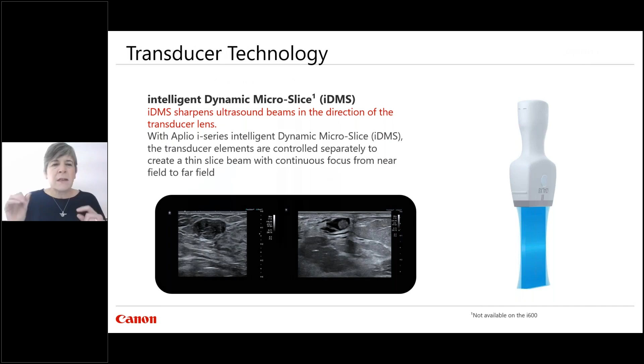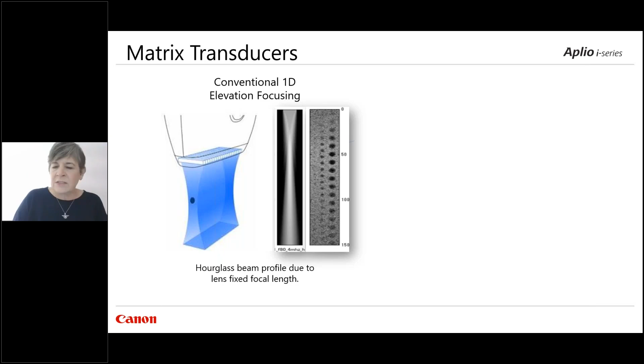And so kind of comparing your standard, what we call 1D array transducer. On most machines, it's one-dimensional. So if you look at the short axis, or what's called the elevation plane focus, there's a fixed focal point that you have no control over. So what you'll notice on some of the other machines, if you're scanning something very superficial, things may be fuzzy. You have your sweet spot, and on high frequency linears, that's about 1.5 centimeters in depth. As you go deeper in the image, you'll see that things also get a little bit fuzzier. With the I series, we have our dynamic microslice technology. So we're using matrix array.